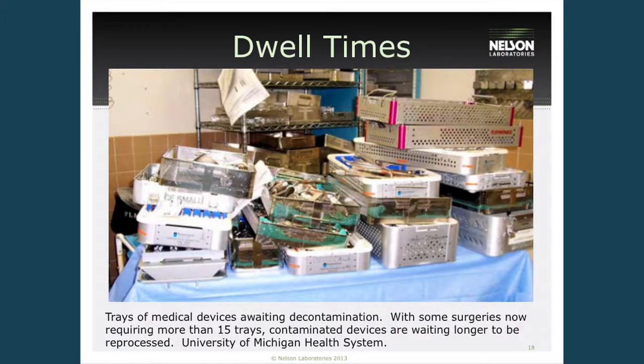So between a dwell time of say 30 minutes to sometimes we are holding devices after the contamination process for 24 hours or even more to make sure that that contamination has dried on fully. This is also causing issues with testing microorganisms in this process. Because the microorganisms die off and then you don't have a starting titer to show that you actually killed or removed the amount of organism from the process.